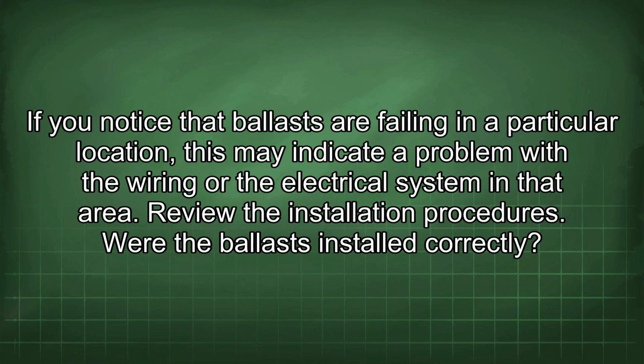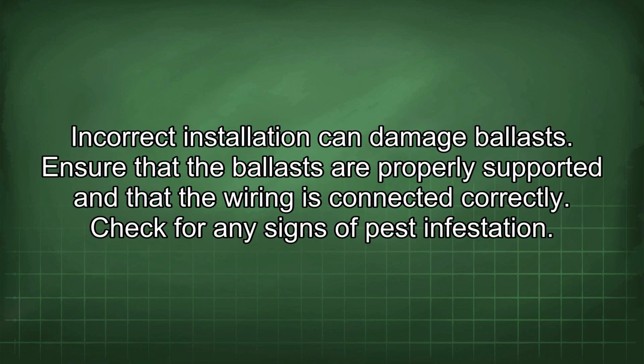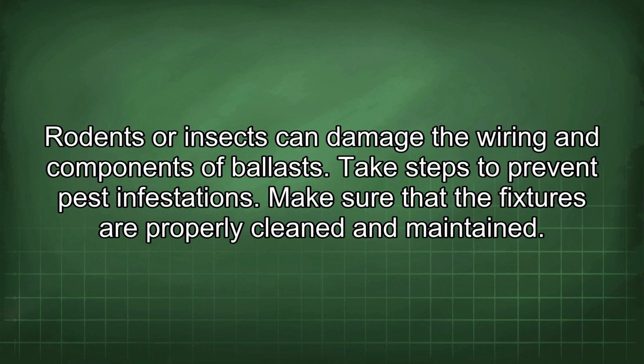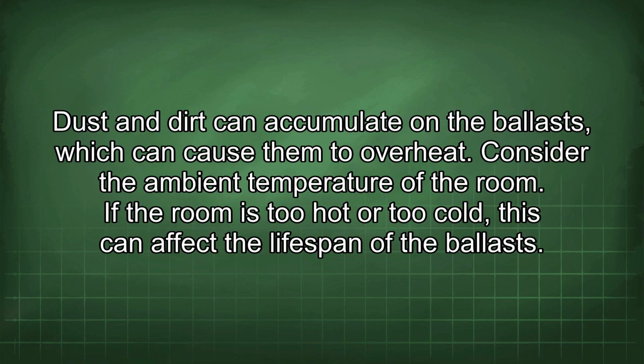Review the installation procedures. Were the ballasts installed correctly? Incorrect installation can damage ballasts. Ensure that the ballasts are properly supported and that the wiring is connected correctly. Check for any signs of pest infestation. Rodents or insects can damage the wiring and components of ballasts. Take steps to prevent pest infestations. Make sure that the fixtures are properly cleaned and maintained. Dust and dirt can accumulate on the ballasts, which can cause them to overheat.